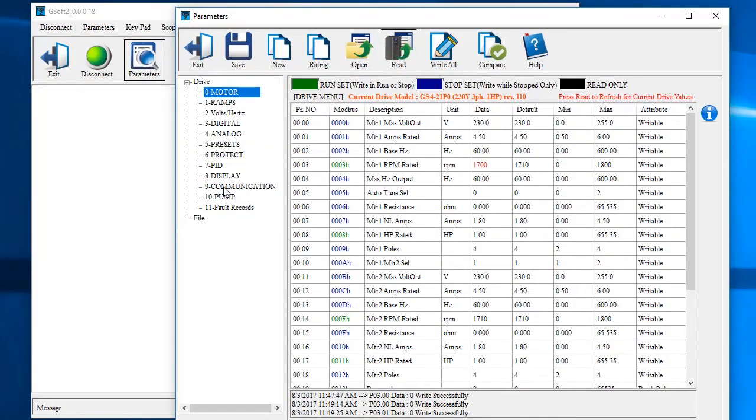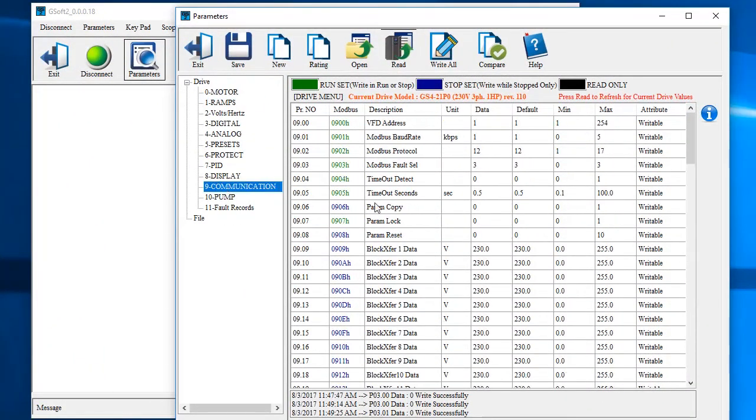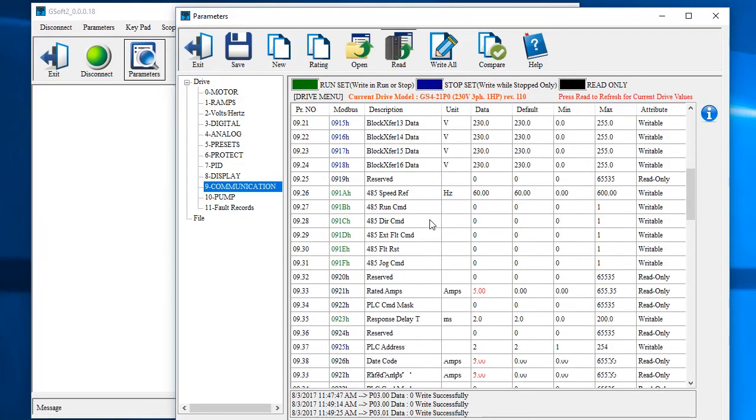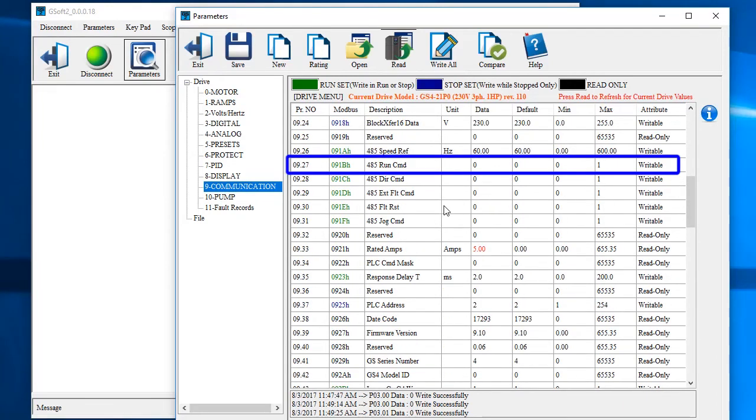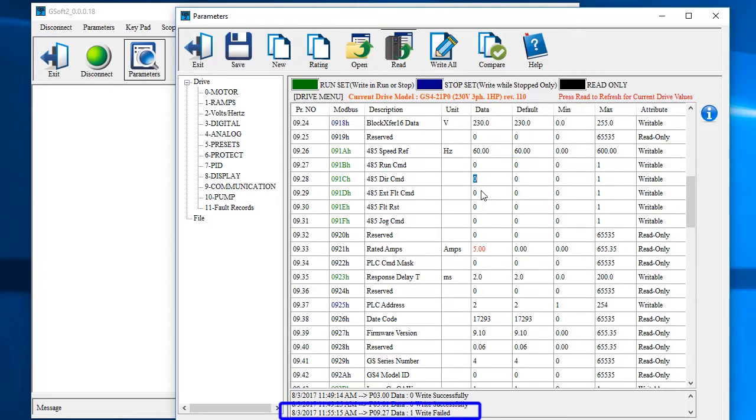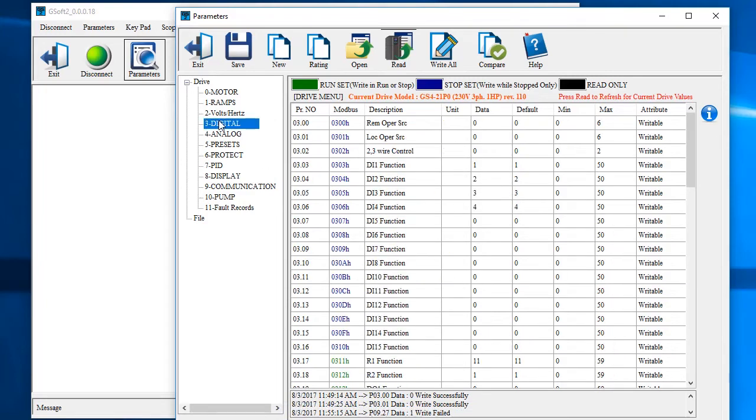Can I enable the drive from here? Well, over here in parameter set 9 I see a run parameter. If I enable it, hmm, the motor didn't go and we got an error. Why? Well, because we haven't told the drive to accept remote run commands from the RS-485 port.